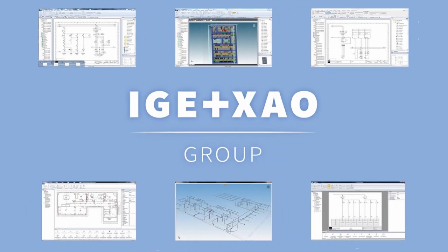Welcome. In this video I will show how you easily can make a thermal dissipation calculation of your panel in SEE Electrical. With a thermal dissipation calculation, you can determine how big the need is for internal cooling or heating of your panel. I show you how to do a thermal dissipation calculation with the PanelThermalDissipation command.